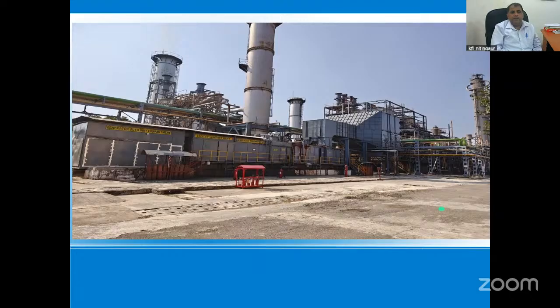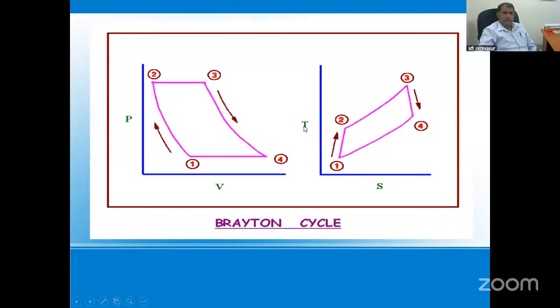One turbine is running, one turbine is standby. We are saying the word standby. Standby means a machine is ready to start. One machine is in running condition and another is in standby condition, means it is ready to start. When there is a fault in the running equipment, another will automatically start. Since it is a process plant, if there is a fluctuation in the electricity, then our whole plant will get tripped. This is the Brayton cycle, all of you know.